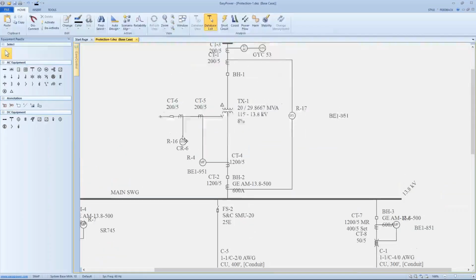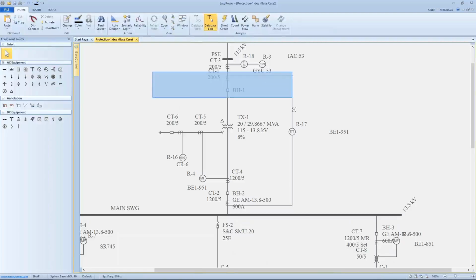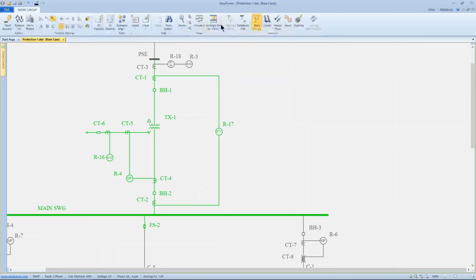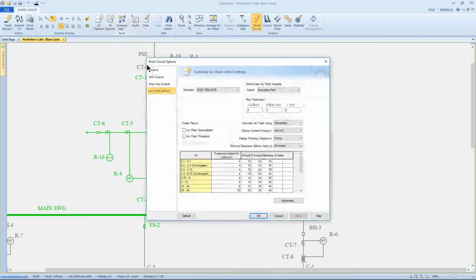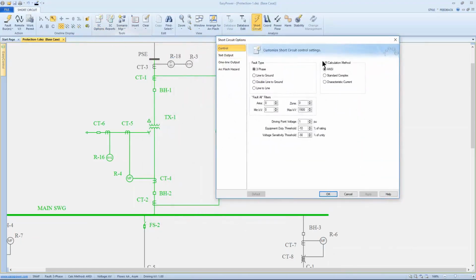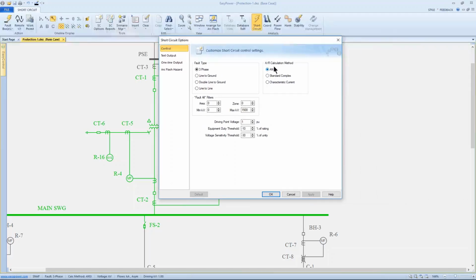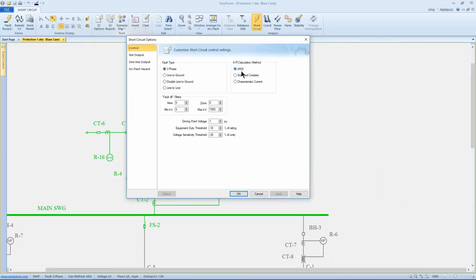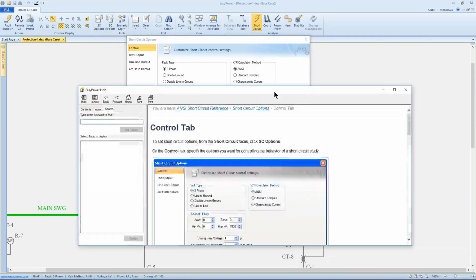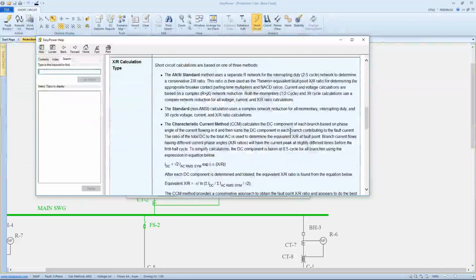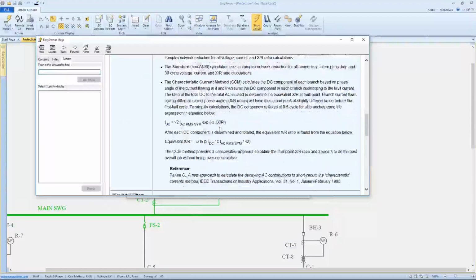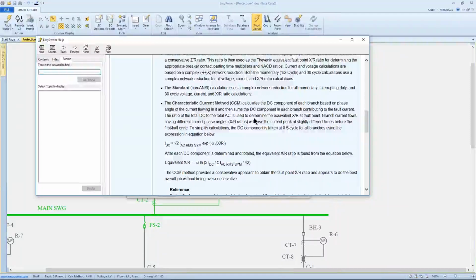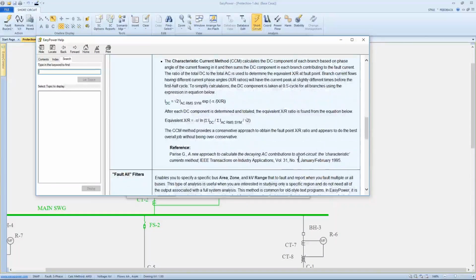Now, one other point that comes up is probably pretty useful to people that get into the details of fault current analysis. We go into our short circuit focus and our control system for short circuits. We actually have the ability to calculate X over R with different methods. By default, we use the ANSI standard, but if necessary, we can also choose the Standard Complex and Characteristic Current calculation methods. These are described in the help system with the X over R calculation described right here. I don't have a clue where I would apply one or the other, but it's described in this particular reference.